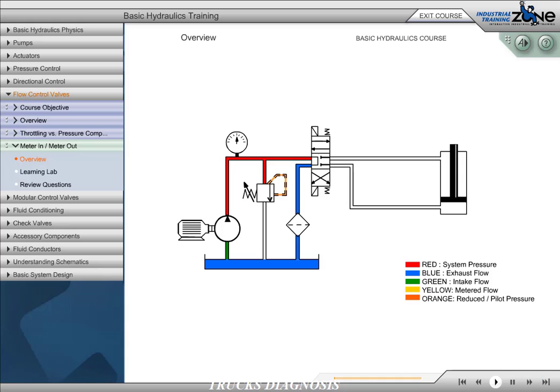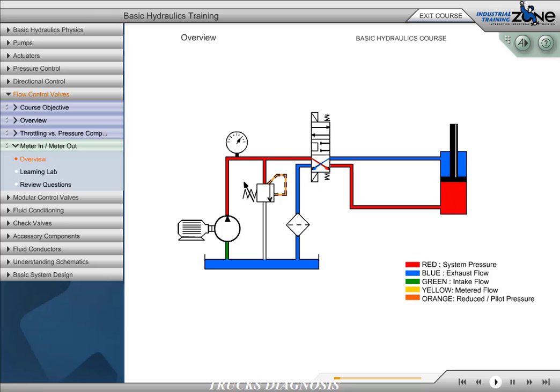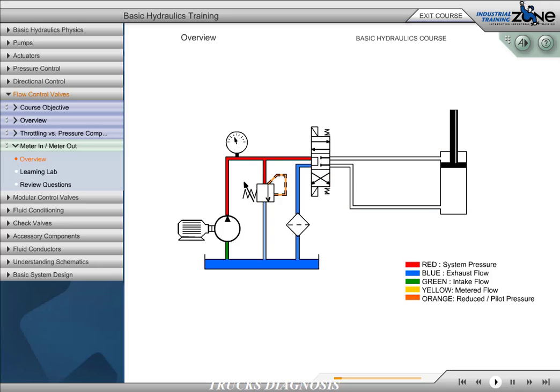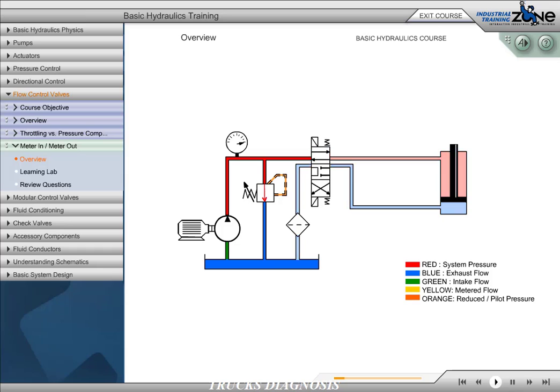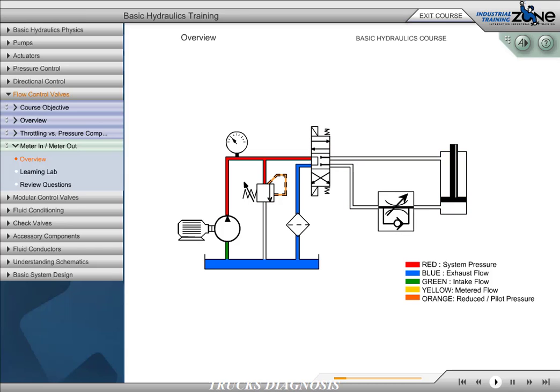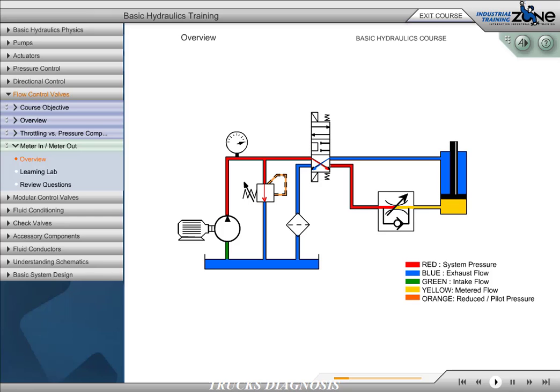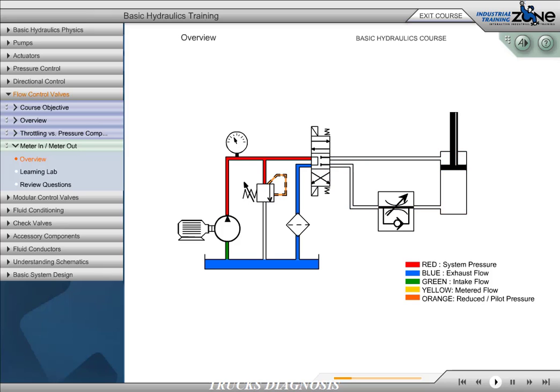Meter-in is the method of placing a flow control valve in such a way that fluid is restricted to the actuator. In this circuit, without a flow control valve, the cylinder extends and retracts at an unrestricted rate. When we place a flow control valve into the circuit, this flow control valve will restrict flow to the cylinder, slowing the extend rate of the cylinder. The check valve allows return flow to bypass the flow control when direction of flow is reversed.